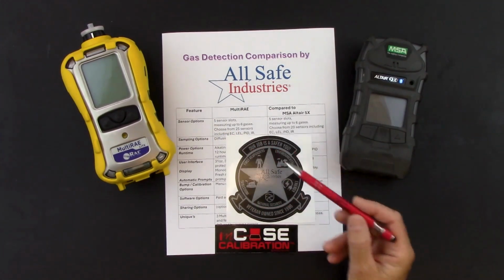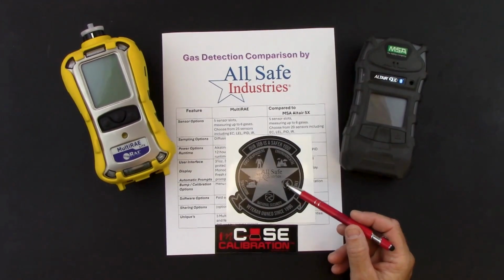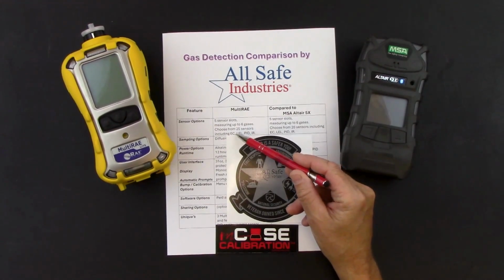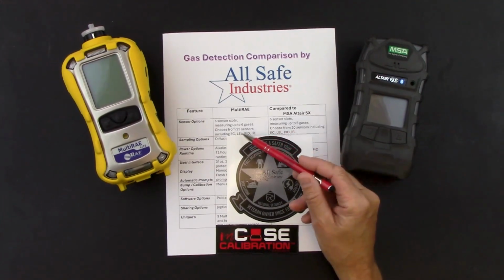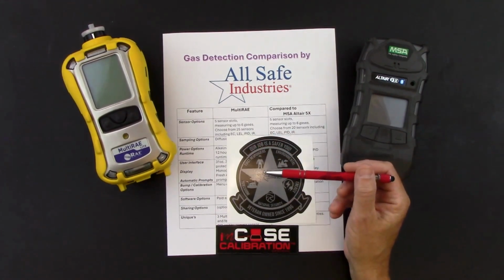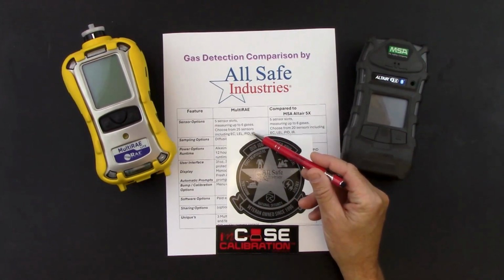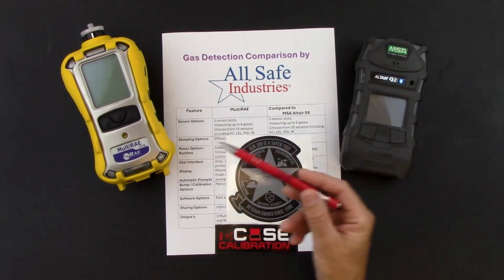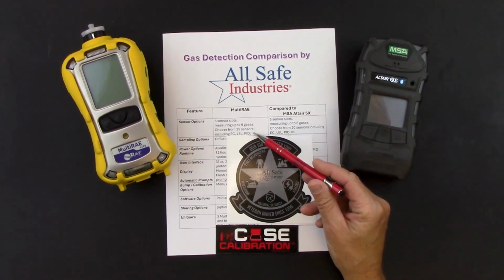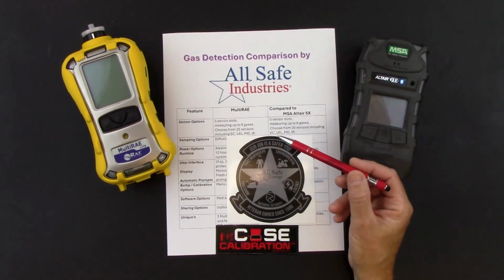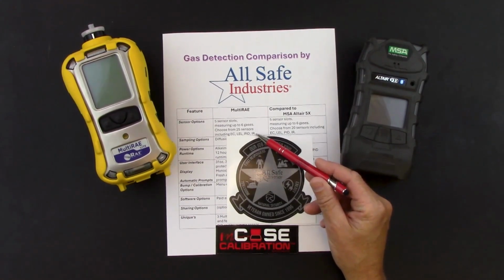We have 25 different sensors that we can choose from, and those would include electrochemical sensors, such as oxygen and toxic gas sensors, a catalytic bead LEL sensor, a PID sensor, and we have 4 different types of PID sensors that we can install in the MultiRAE family, and then IR sensors for both combustible gases and CO2 carbon dioxide.